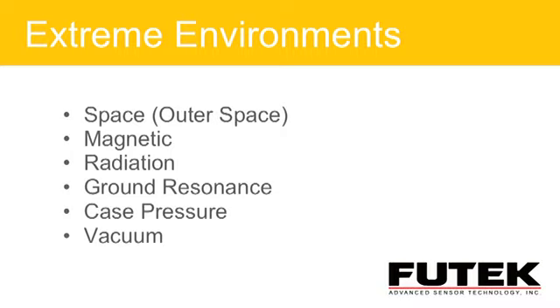Ground resonance. This is extremely critical when it comes to low capacity units. You've got a 10 or 20 gram unit and you're trying to measure 1 milligram, 3 milligrams. That ground resonance will definitely throw you off. That can cause a huge problem. So is there something that can be done to help? Yes, there may be some specific test fixtures that you can utilize. Case pressure, and this is one we're starting to see a lot of, especially in oil and gas, the downhole, where customers want very high case pressure, 10, 15, 20,000 psi on the outer cover, on the outer casing, without affecting the performance of the unit. Extremely challenging to do, but we're always up for a good challenge.